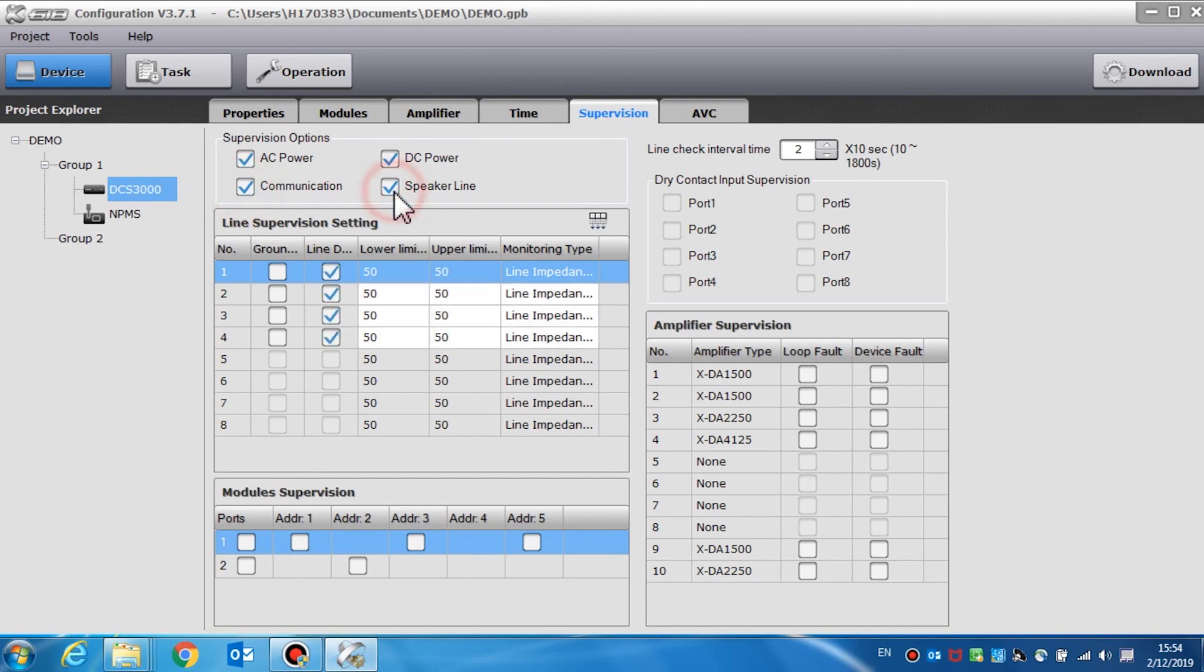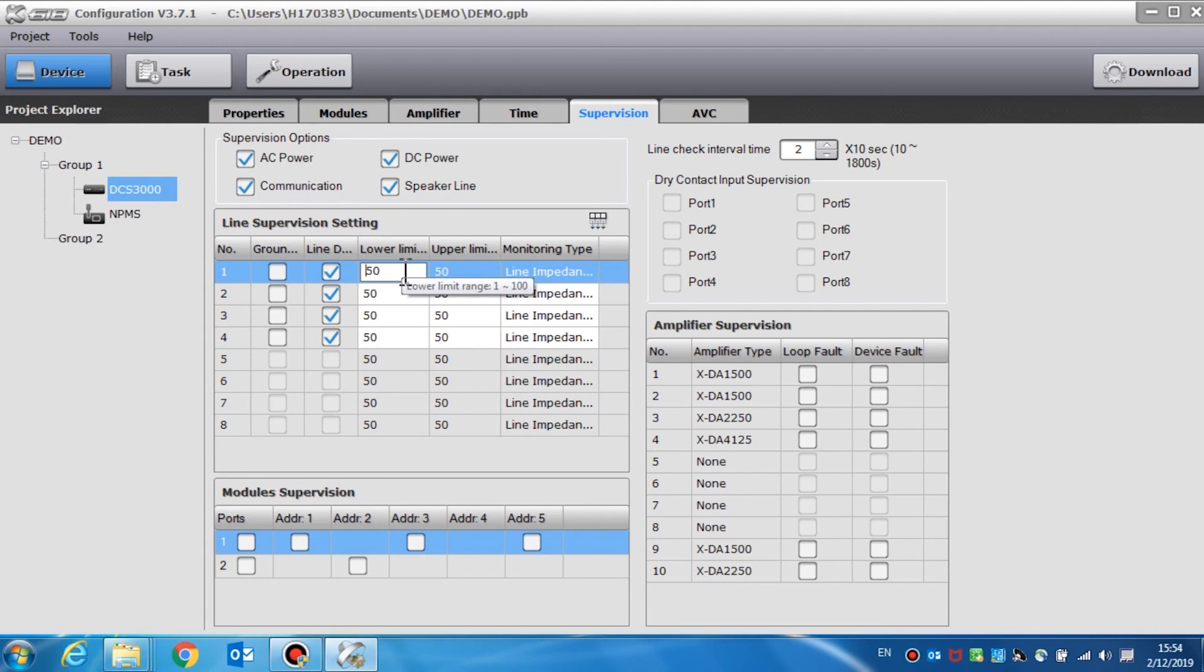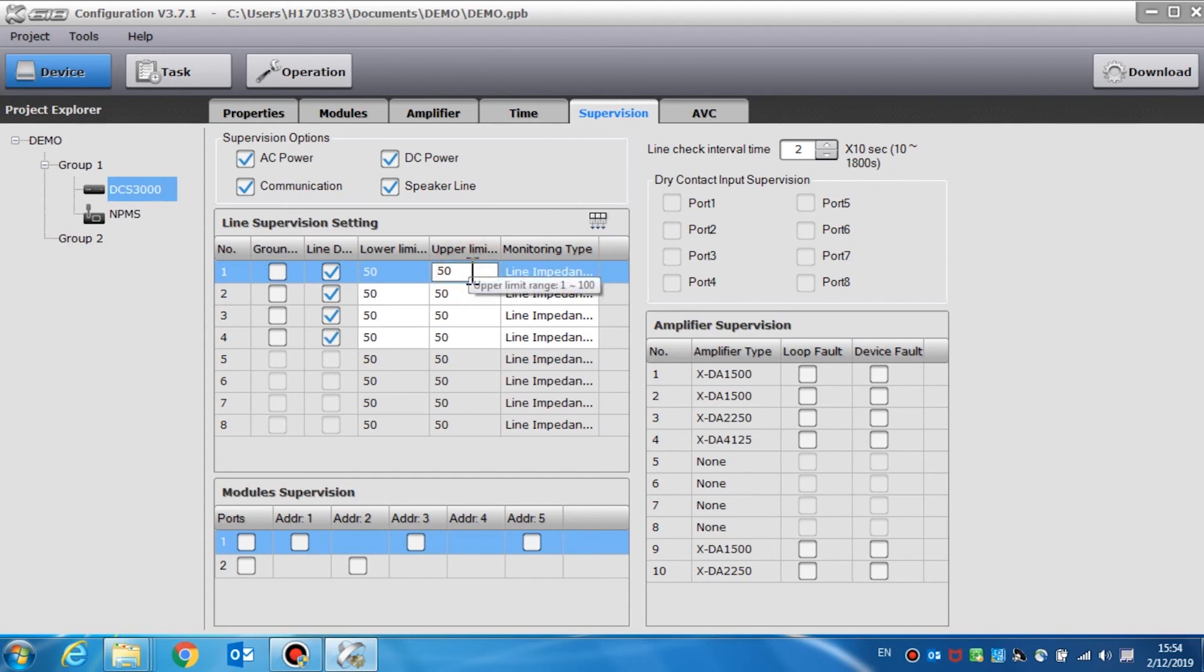The second part is line supervision settings. If line impedance is enabled, users can respectively enable or disable the line supervision function of the enabled speaker lines and set the line tolerance parameters. When the line impedance is lower than the lower limit, a short circuit will be found in the speaker line. When the impedance is higher than the upper limit, an open circuit will be found in the speaker line.